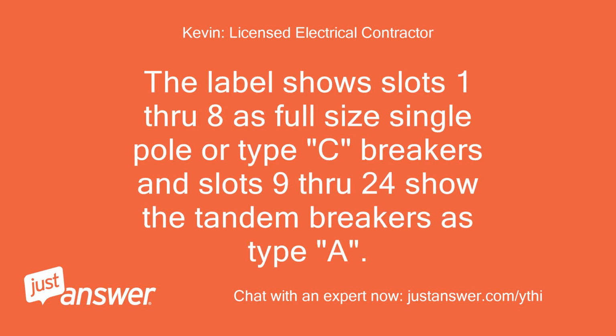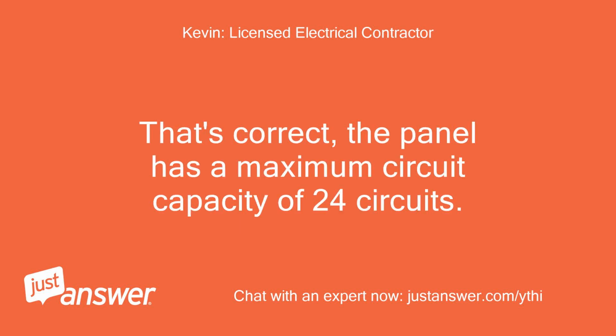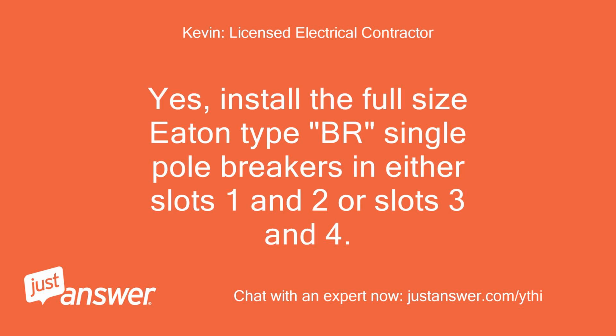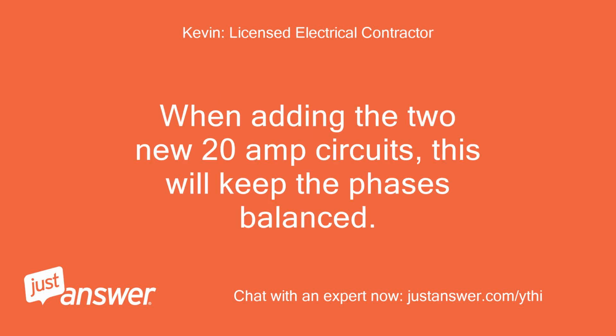The label shows slots 1 through 8 as full-size single pole or Type C breakers and slots 9 through 24 show the tandem breakers as Type A. That's correct, the panel has a maximum circuit capacity of 24 circuits. Yes, install the full-size Eaton Type BR single pole breakers in either slots 1 and 2 or slots 3 and 4. When adding the 2 new 20 amp circuits, this will keep the phases balanced.